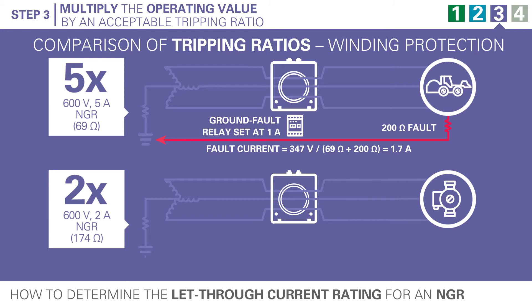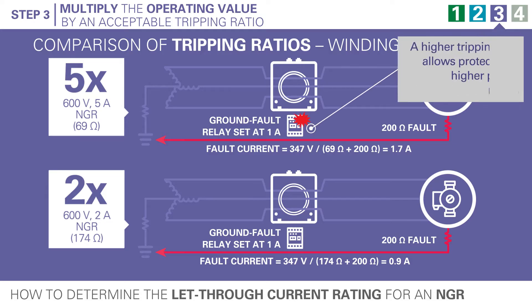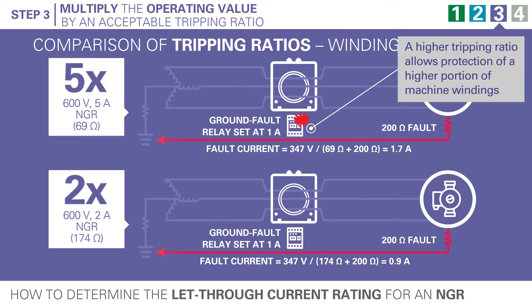When a ground fault occurs internal to a motor, the added impedance of the motor winding will also limit the amount of ground fault current that can flow. Because of this, a higher tripping ratio is necessary to detect high impedance faults and provide machine winding ground fault protection. In the example shown, the system with a tripping ratio of five will protect the equipment, and the system with a tripping ratio of two will not.